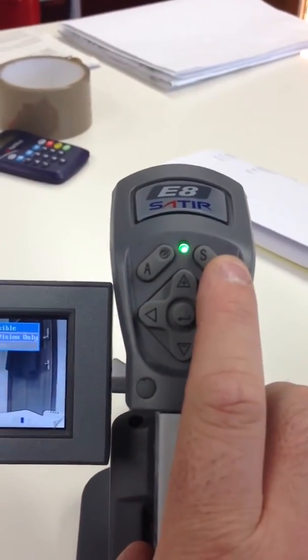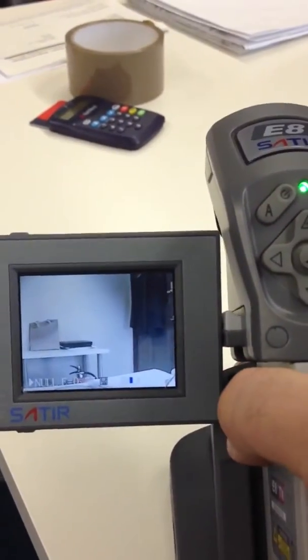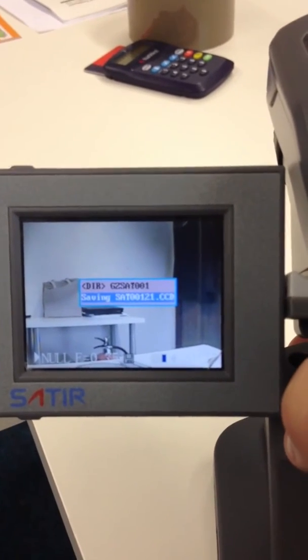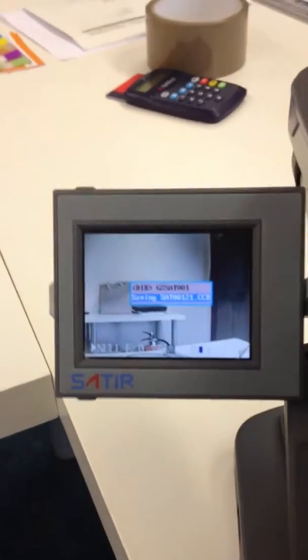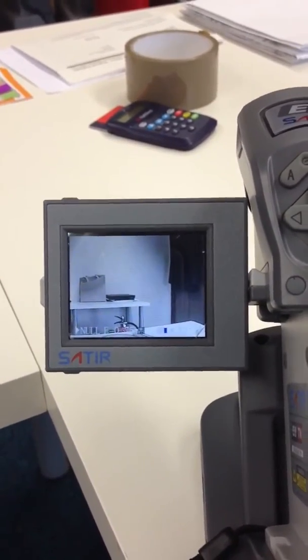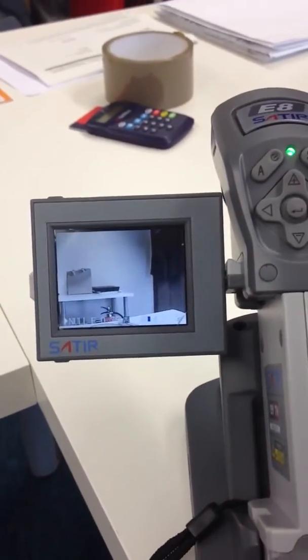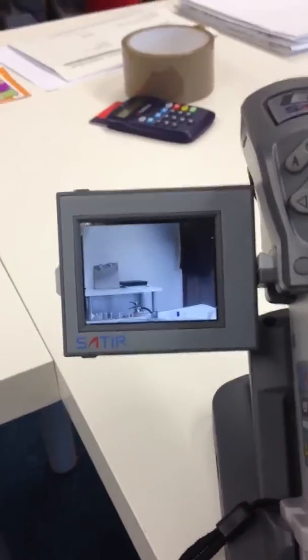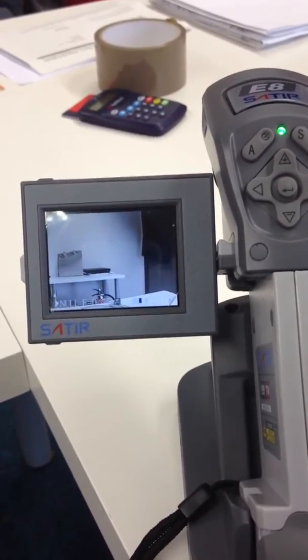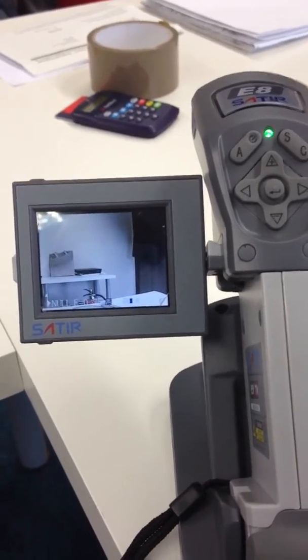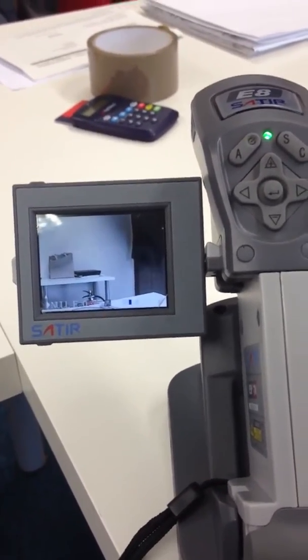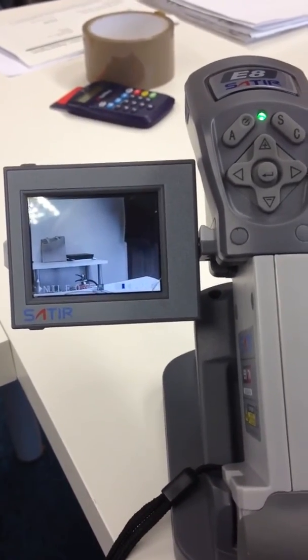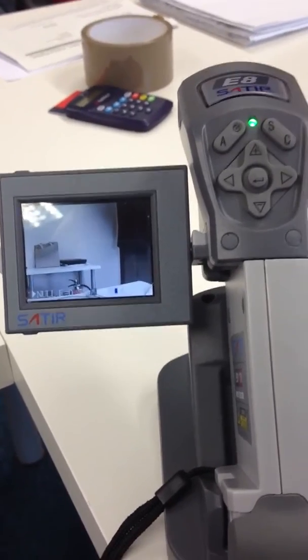If you want to go back to the main menu, just keep pressing your C. Once you've found what you want, put your trigger on, aim your camera, take the picture, write that number down in its entirety, and then also write where the location is of the item that you've just taken a photograph of, the description of the location, and the designation. If it's a distribution board, DB1, etc., located within the main stores, the actual item or description could be the main switch, the MCB, the busbar chamber, it could be many different things. If you're pretty descriptive, it makes your report a little bit better.